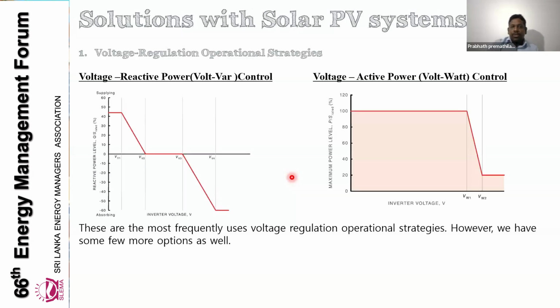The first solutions, actually, we all know, as I explained, the biggest challenge at the LV network is the voltage issue. That we have solutions: voltage regulation operational strategies. Actually, we call them voltage control mode supports. These are two very famous supports: voltage reactive power, volt-var control, and the volt-watt control. If the voltage is in the normal range, we don't request any reactive power support. But if the voltage is high, we request the inverter to absorb the additional reactive power and get the voltage back to the normal situation.